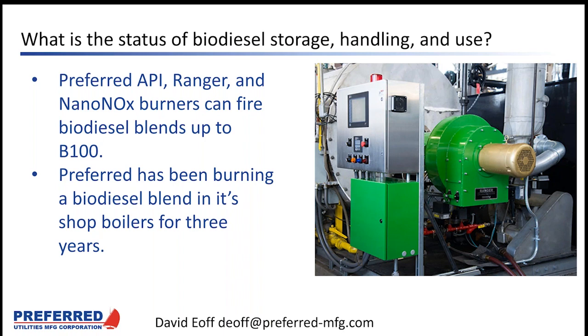The differences aren't large, but we just need to make sure that we do the math and make sure that, if we're real close to the next pump size, the next flow control valve size, or the next fan size, that it can accommodate burning biodiesel.